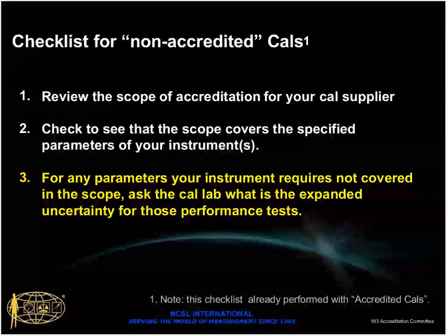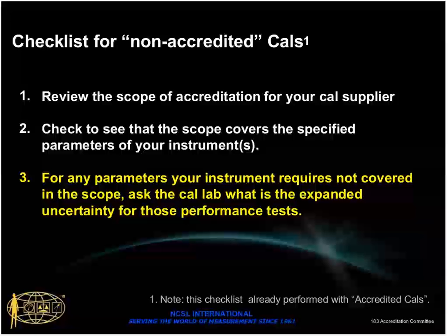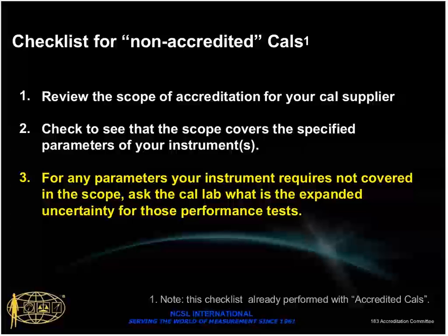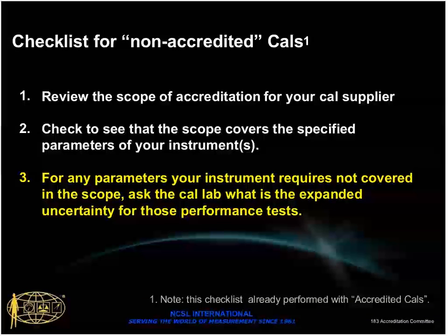And in the scenario where a supplier offers calibration service which is outside of their schedule of accreditation, if I were in that situation, I would be asking that calibration lab, for this instrument model XYZ, what is the expanded measurement uncertainty that I can expect for this instrument? Now, if you're not used to asking that question, you might wonder how reasonable that is. And I can tell you from my company's standpoint, that's a very reasonable question, and it's a very simple matter for us to go get a sample calibration report, pull that up and share that with you and say, here's the same model for a different customer.